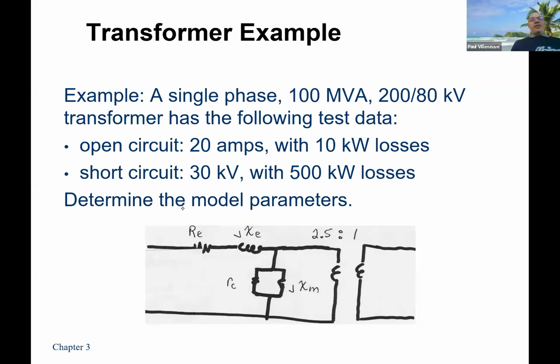I gave you V because the open circuit test means run it at rated voltage. So you're either going to use 200 kV or 80 kV. Right? It's just going to be one of those parameters. So you do have the voltage. You just have to pick which one of those two.